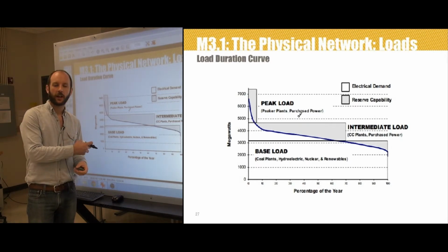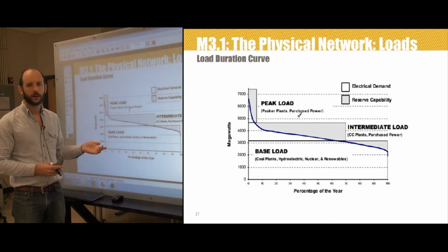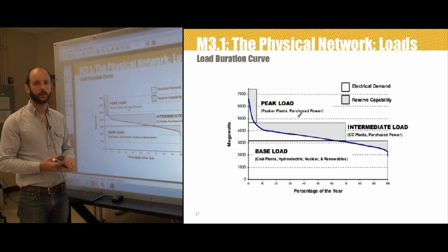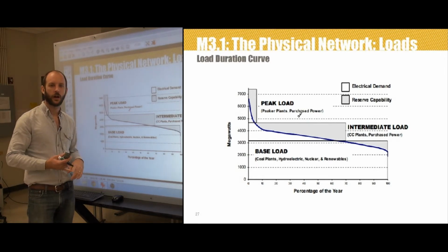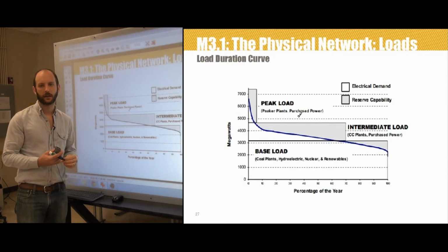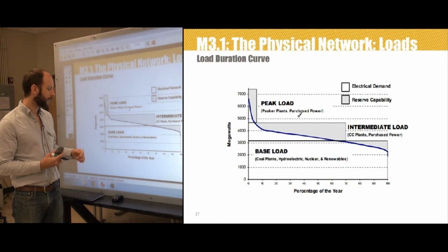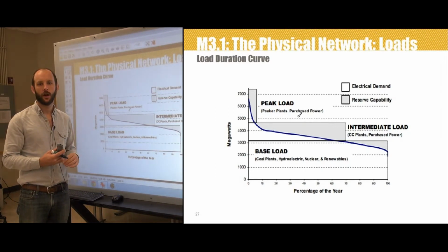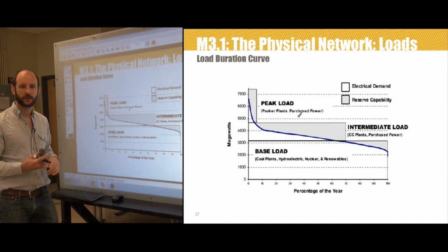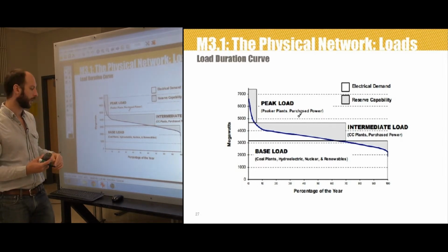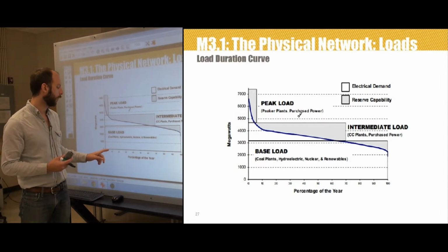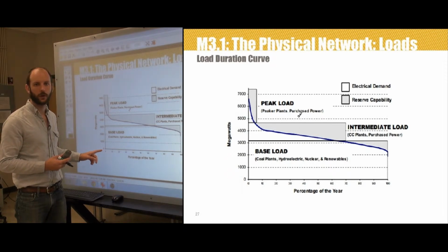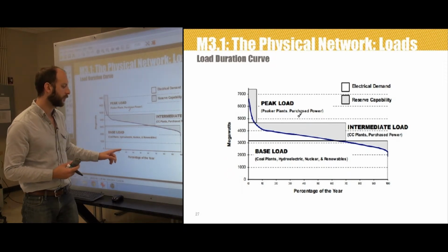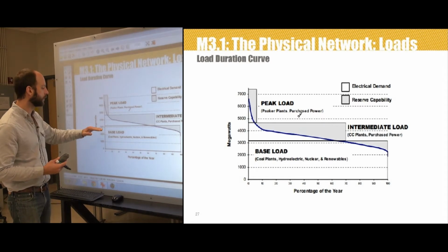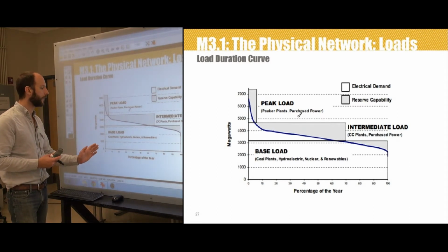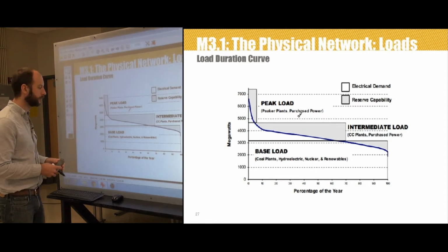Another way to look at that load data that we just presented is what's called a load duration curve, which is a plot of the percentage of time a load is at a given demand level. The electric demand is plotted on the vertical axis, and the percent of occurrences are plotted on the horizontal axis. So what we've got is an electric load, the percentage of the year that the load is at a certain demand level, and then we've got demand level on the y-axis here.